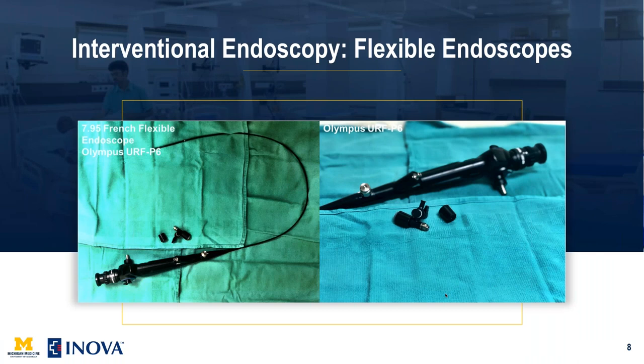Here are examples of the scopes. The 7.9 French flexible scope is a reusable scope used by urologists. After use, it can be sterilized, autoclaved, and reused. Most scopes have the same basic setup: an end where the camera attaches for connection to the screen, an area where the light cable attaches to provide light to the scope, and a channel where fluid can be supplied for continuous irrigation and where a variety of devices — such as thrombectomy devices, baskets, or lasers — can be placed.